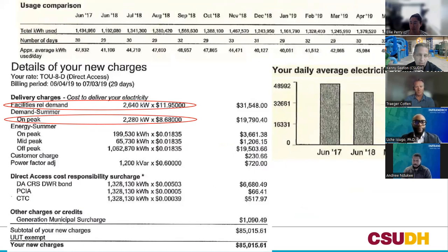Here is 2019. In 2017, we had 1 peak demand charge, so it was the worst 15 minutes for the entire month. Didn't matter what time it happened. Then we went to time of use peak demand charges. So now we have 1 peak demand charge that was $11.95 for the worst 15 minutes of the month, and then we had an on-peak, which was probably from 4 to 9 or 5 to 8 back then, not sure. If you set a higher peak, you also got that at a different rate, so you were paying twice. One got lowered, but then you had two, so it equals out to a high rate at the end. Next slide.